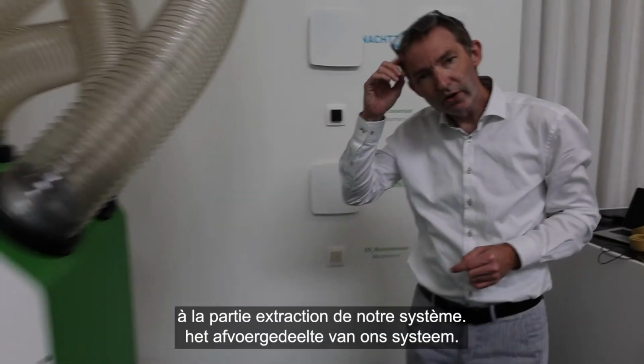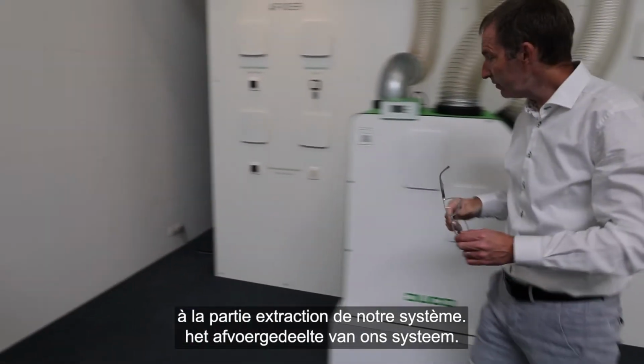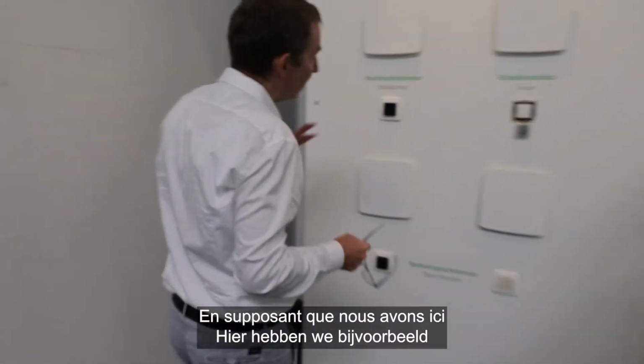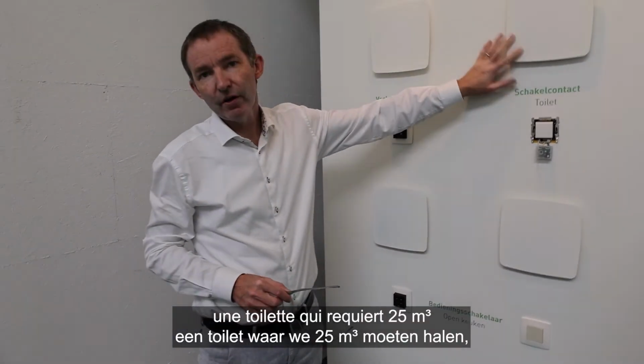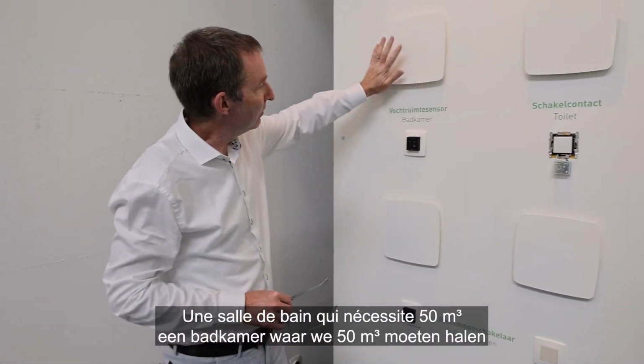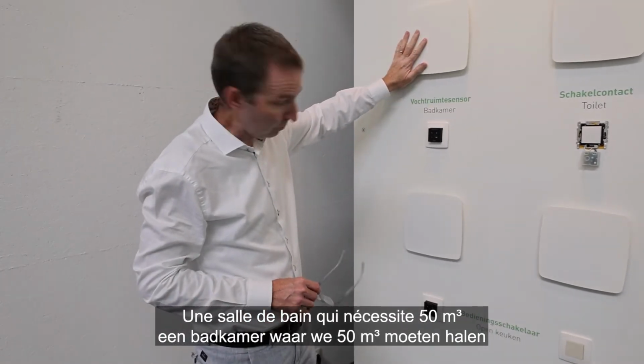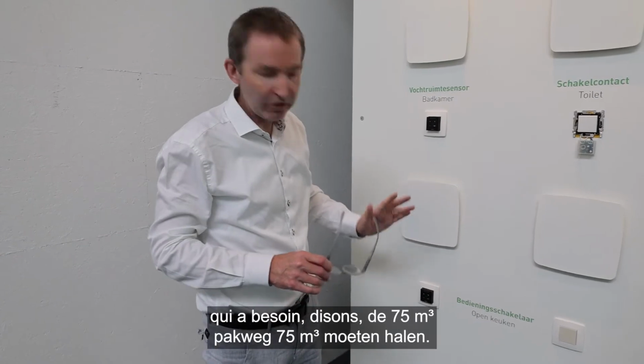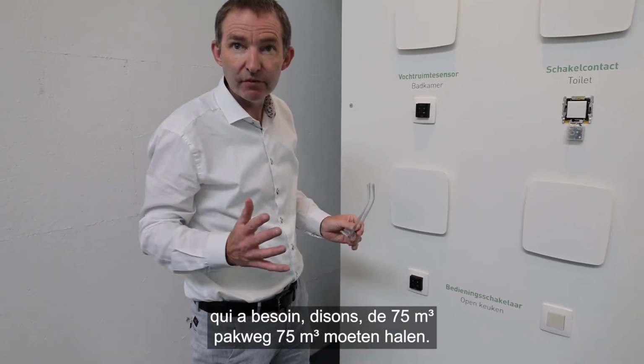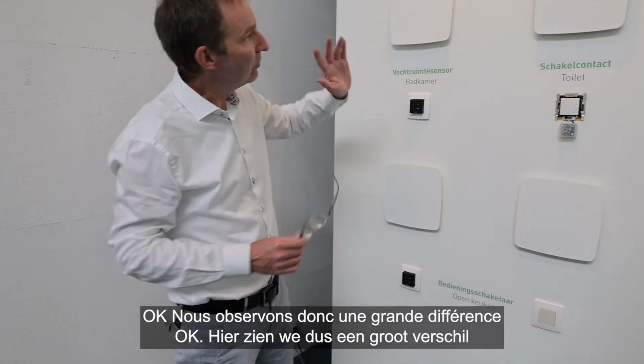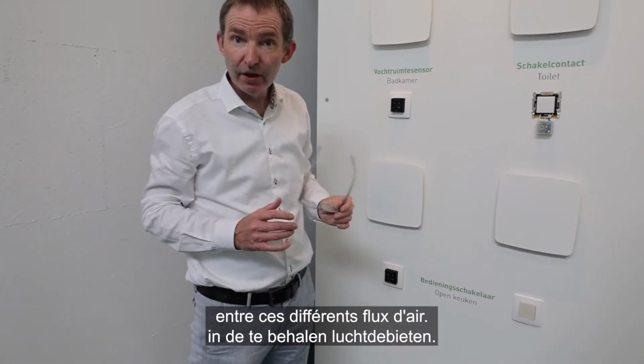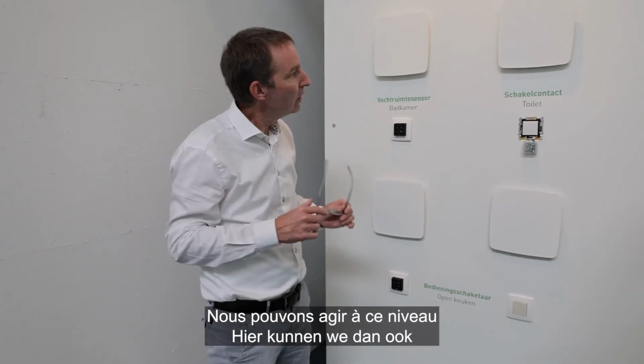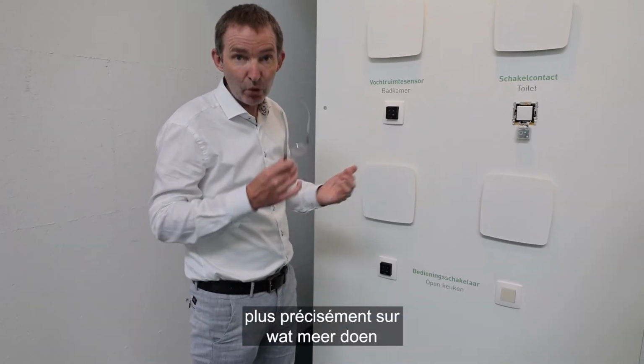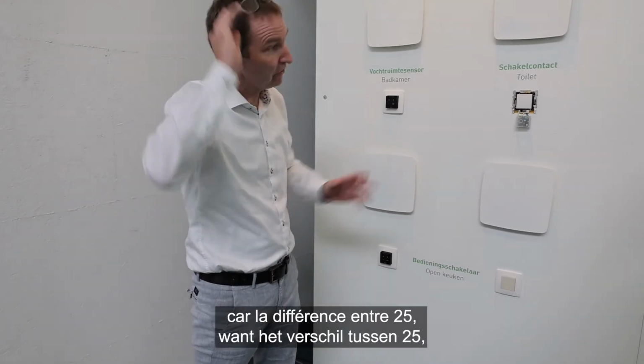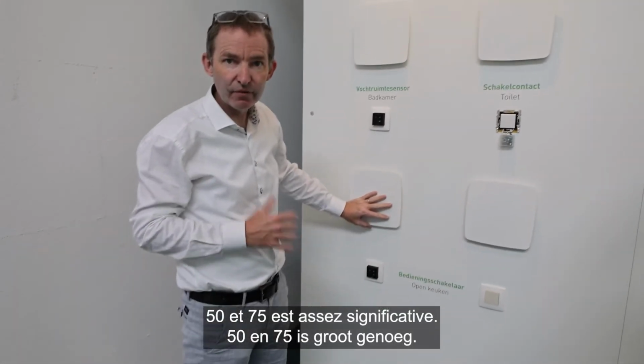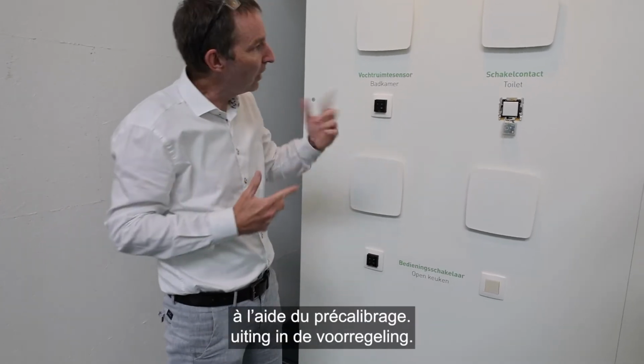If we then move on to the extraction part of our system, let's suppose that here we have a toilet which requires 25 cubes, we have a bathroom which requires 50 cubes, and we have an open kitchen which requires, let's say, 75 cubes. So then we see a big difference between these different airflows. Here we can do something more significant in respect of pre-calibration, because the difference between 25, 50 and 75 is significant enough, and we will reflect that by means of the pre-calibration.